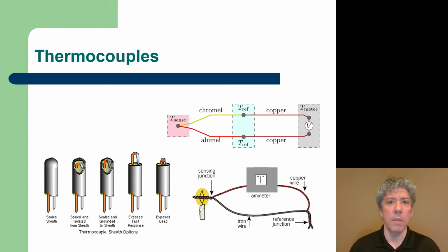If you need something to protect the thermocouple from the environment, but it's okay for that junction to be grounded, then you can use the middle option, which is where the thermocouple is sealed and grounded to the sheath. Now this will have improved performance in terms of responsiveness to changing temperatures around the sheath. Now another option is the exposed fast response type. Now this type, of course, just leaves the junction exposed but protects the wire leading up to it. And then there's the option of an exposed bead.